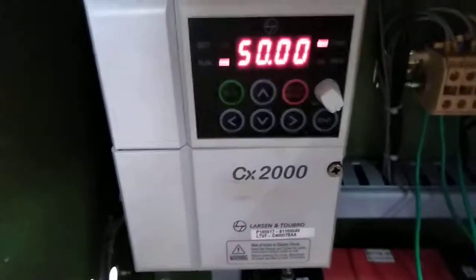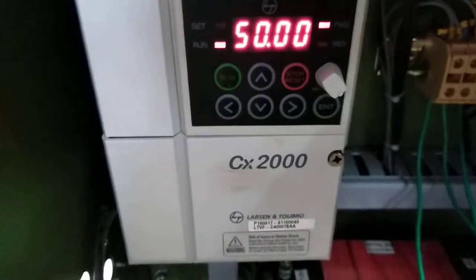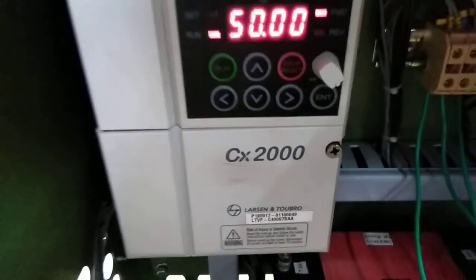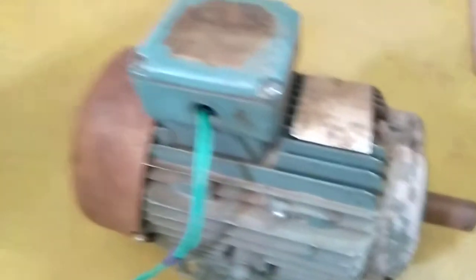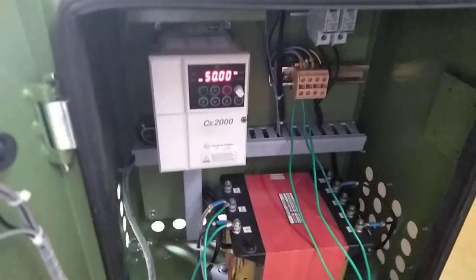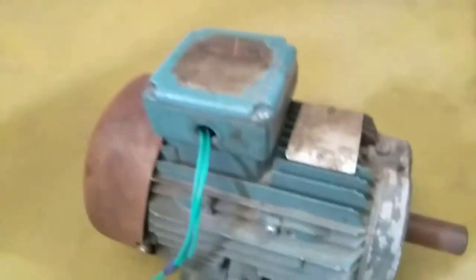The supply is given to the L&T VFD drive. So the drive will generate three-phase supply that is given to the three-phase motor. So automatically, using the drive or our panel, single-phase supply is converted into three-phase supply to run the three-phase 3HP motor.